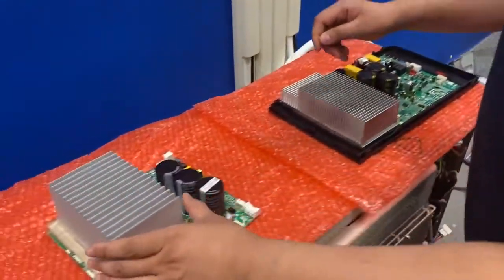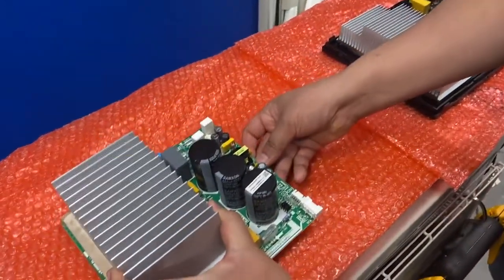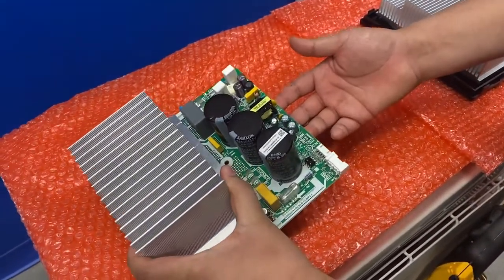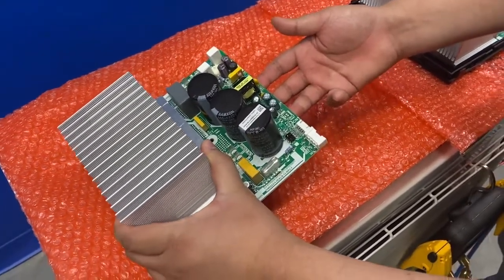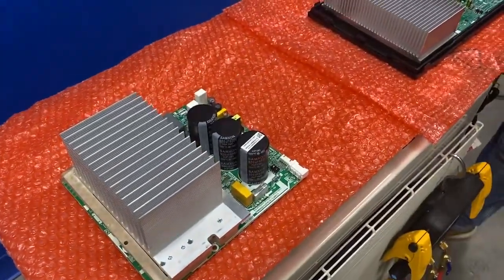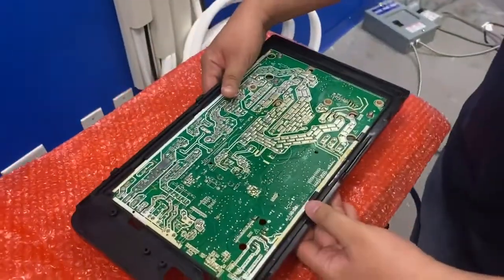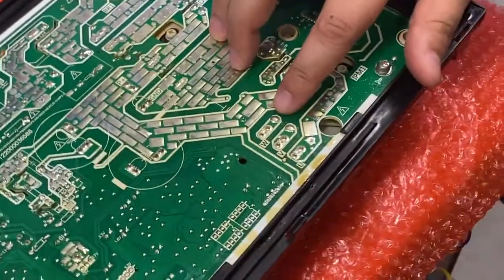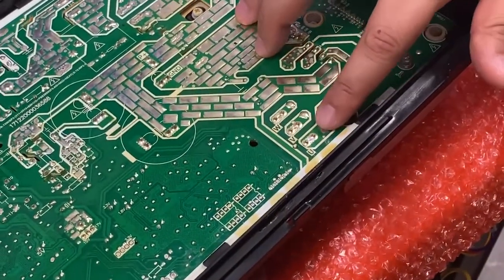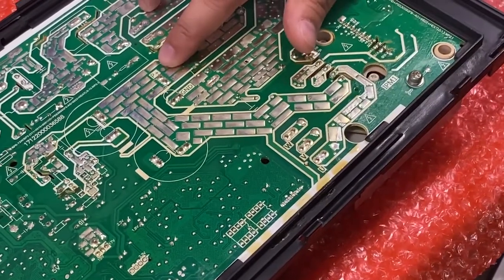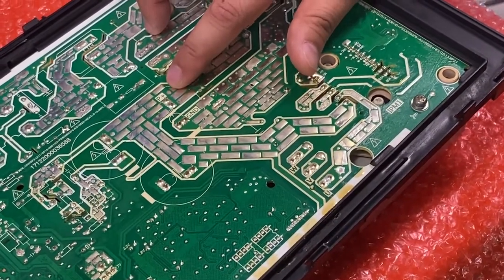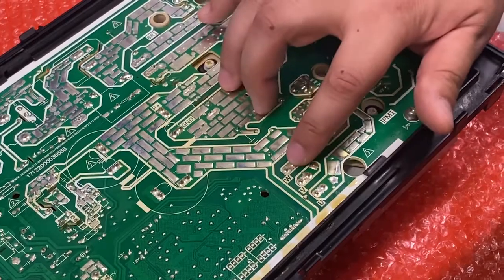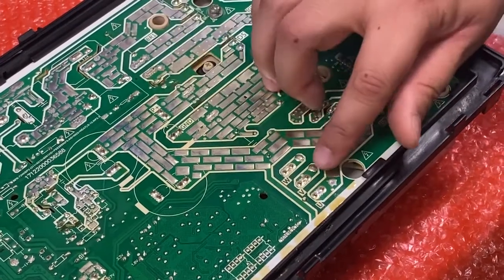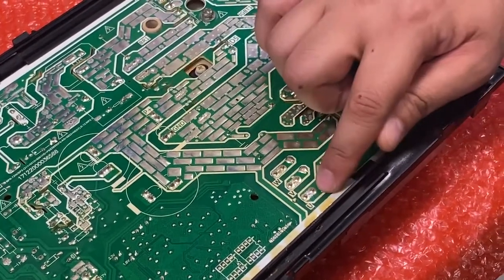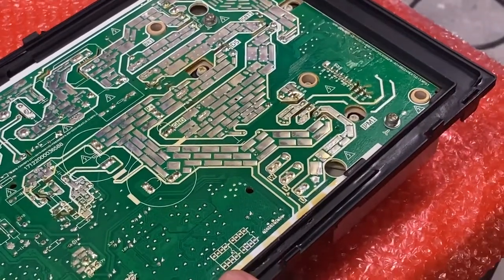Over here I have an IPM board by itself, and these come standalone on our larger BTU units. To check the unit, we're going to locate W, V, U, and P, and with your meter, you're going to check between P to W, P to V, P to U, and make sure all the values are the same.